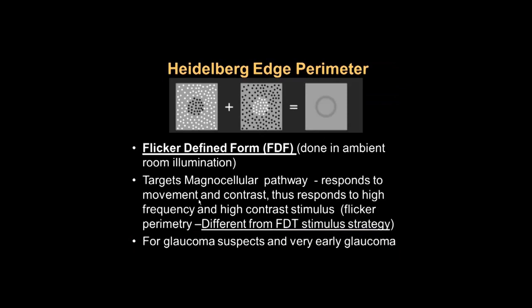Let's look at the Heidelberg Edge Perimeter. Besides regular white-on-white testing, it uses something called flicker-defined form (FDF). This is what the patient sees, and it can be done in ambient room illumination — this instrument can be wheeled into the patient's room. It targets the magnocellular pathway; the response to movement and contrast is what is called flicker-defined form. It is different from the FDT stimulus strategy and is most useful for glaucoma suspects and very early glaucoma.